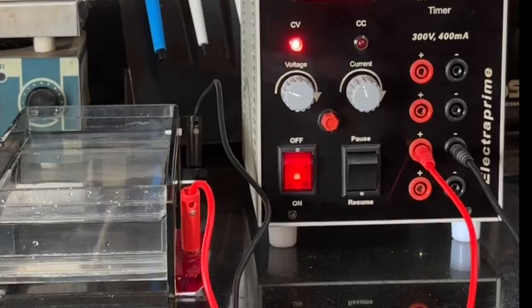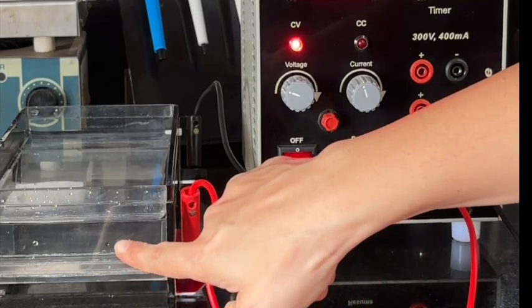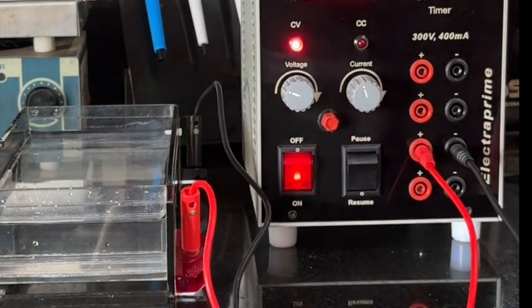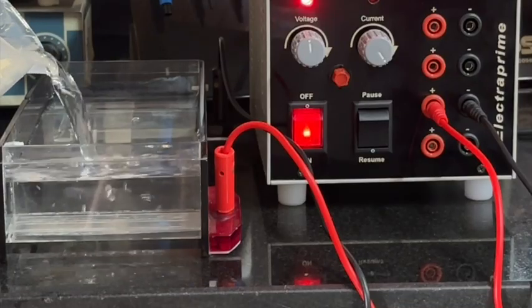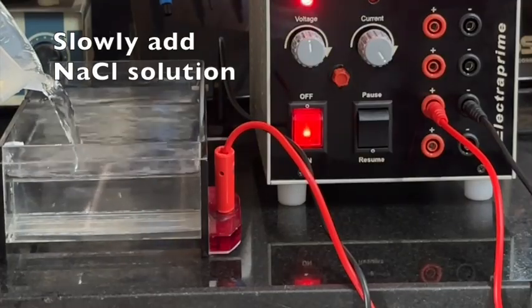Cause number 6. Wrong composition of the buffer. This is one of the most common causes for the current reading showing 00. Check and recheck the buffer composition. An alternative for testing is to use distilled water instead of a buffer and then slowly add a NaCl solution to the buffer tank.